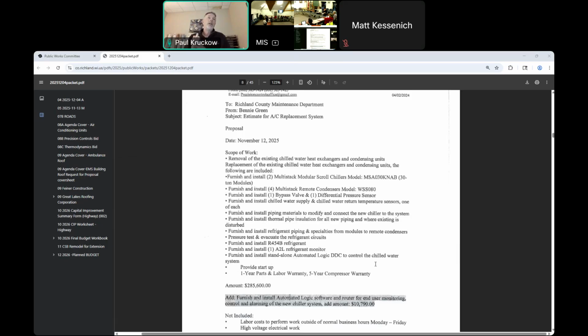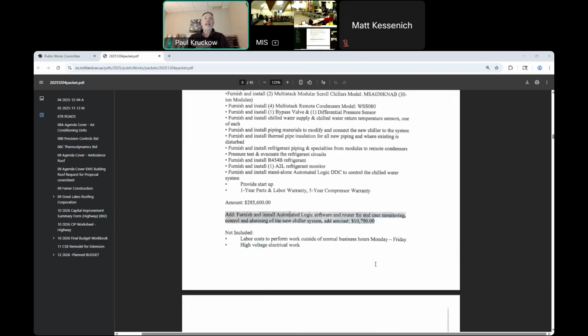A little further down, I put in an add as an option. If you wanted to monitor the system from a front end or remotely, if you wanted it to send out an alarm to somebody if the chill water failed, say on a holiday or a weekend, whatever it was. In this case, hopefully we're not going to have a failure, just because of how this system functions and what we selected here. But if there was a loss of power for some reason, you'd know that through other means, I'm sure, but this would give you the capability to remotely monitor the chill water system. It's not necessary. I put it in there as an add if it was of any interest.